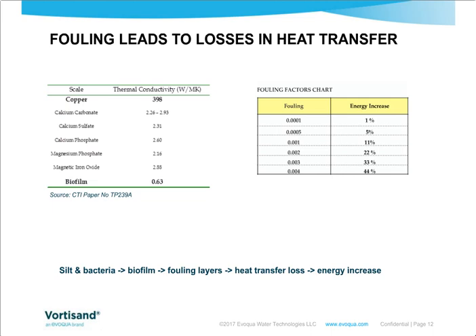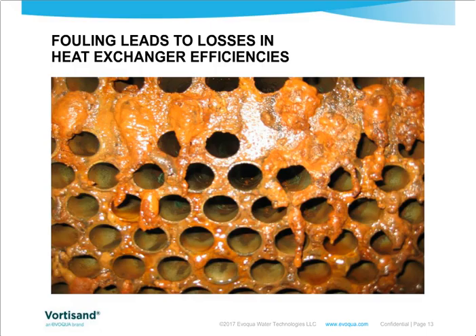And as you can see here on the right, the fouling factors chart, as your fouling factor increases, you can see some data that actually show the increases in energy that would be caused. So if you want to keep your chillers or cooling towers or hot loops maintaining the same delta T, you're going to need to continually add more and more energy to counteract that biofilm growth. So it's important to understand how fouling leads to heat transfer loss. And here's just an extreme example of some biofilm growth in heat exchanger applications.